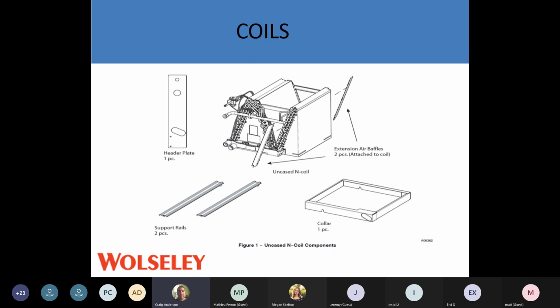And a lot of the time, if the guy's not familiar with the N coil, he is installing it like he's installing an A coil, putting the channels on the side, 1.5-inch, 2-inch channels, screwing them to the plenum, sliding the coil in. So what's happening is they are blocking off the right part of the coil fully, or they're blocking it half off. So be very mindful when you're installing it that you're not blocking off the right-hand side of that coil.